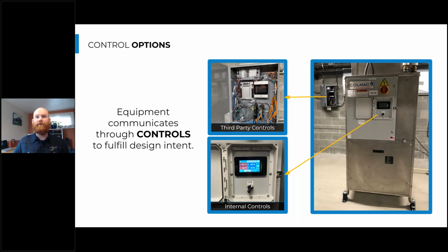And so we have flow meters, additional temperature sensors beyond control, and a few other things in this system. And so we utilize a third-party control system that can actually communicate with the heat pump, pull data from that heat pump, and report it to a cloud so that we can access it from our desk and track how the system is operating, and report on that to our utility partners who are working with us in this example.